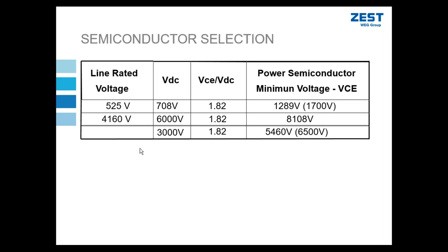The same principle applies to this topology in the medium voltage drive. If I have a line rated voltage of 4.16 kV, similar to what we've just looked at as an example, and my topology was the same as a low voltage drive and I did not have that neutral point, the DC link voltage I would need to switch on any single IGBT would be 6,000 volts. If I applied my safety margin of 1.82 to that 6,000 volts, I would need an IGBT rated for 8,100 volts. Okay. It does not exist. There is a lot of research into 11 kV IGBTs, but at this point, they have not hit a breakthrough. So the highest rated IGBT in regular use is a 6.5 kV IGBT.